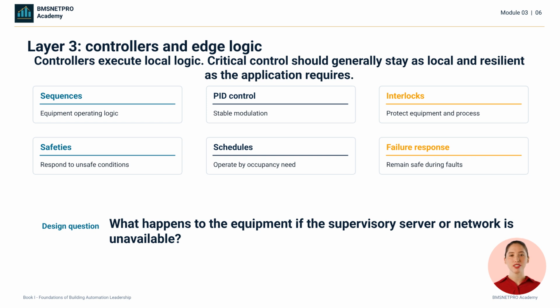Layer 3 is where controllers execute local logic. Typical functions include equipment sequences, PID control, interlocks, safeties, scheduling, alarm evaluation, trends, and failure response. A critical idea in the book is that critical control should generally remain local and resilient. Loss of the supervisory server should not automatically disable essential equipment control. During design and troubleshooting, always ask what happens when the network or front end is unavailable.